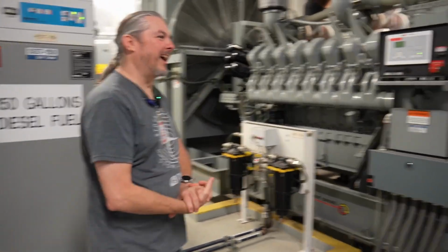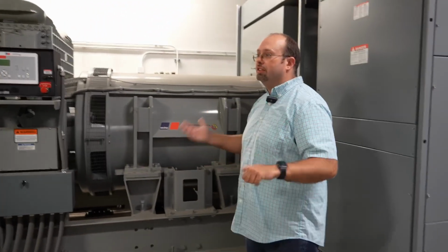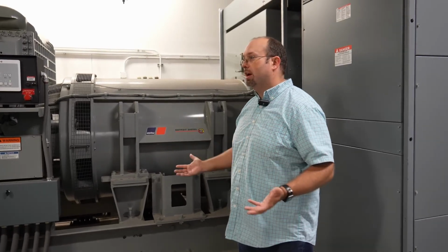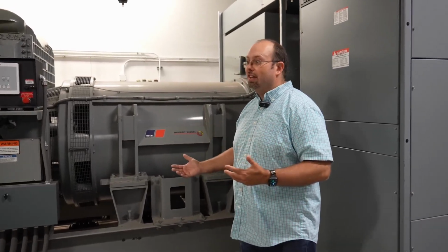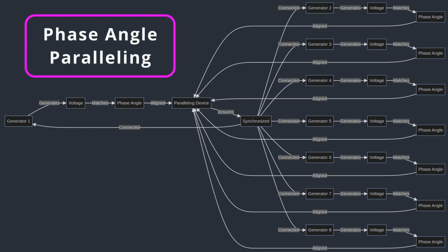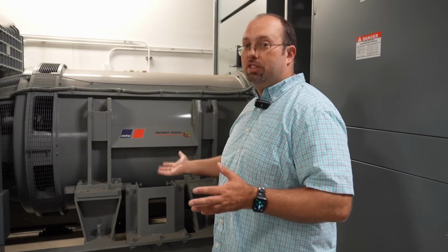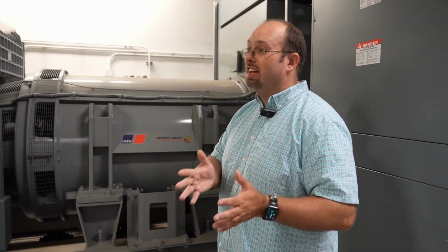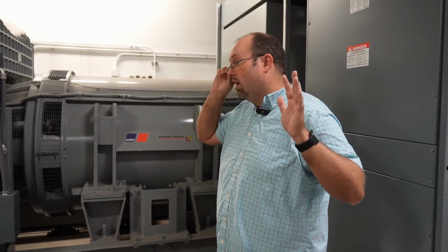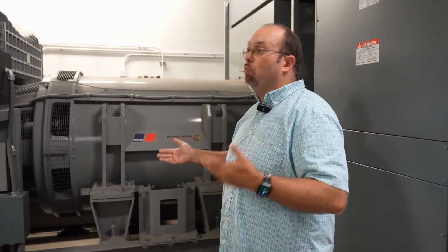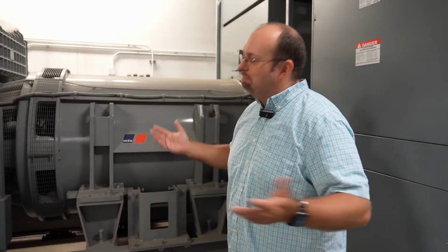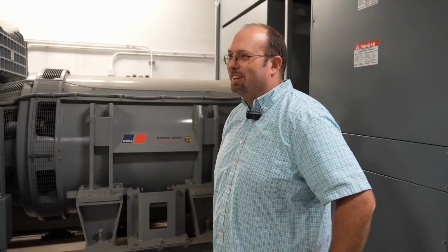When you're dealing with a building block of this size, facilities range from a couple megawatts up to dozens of megawatts, and one generator isn't big enough to handle what you need. So you have busing or paralleling equipment. If the first generator attaches to a bus with a bad waveform, it can set the standard, and when the second generator latches on and can't match that standard, it fails to latch on. You could end up with only one of maybe seven generators attached, and you can't run an entire data center with a seventh of the critical power generation.